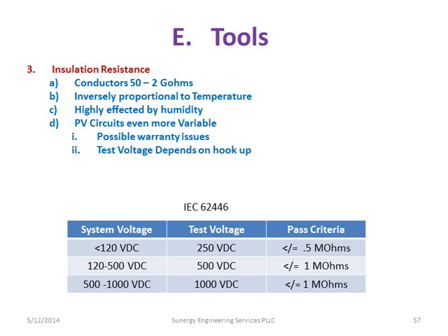So the IEC has kind of a very slack standard. They say that if it's 120 volt or less system voltage, you test it at 250 volts, which I think is a good recommendation. I've read in RE Wrench where people are saying, well, my Megger goes up to 10,000 volts, I'll just make it 10,000. That should be okay, right? Don't forget that the system's rated at 600 volts DC, so you want to be a little careful about pushing that too high. But they say basically that it has to have at least a half megaohm or greater resistance. And oftentimes a wire will come out in the gigaohms.